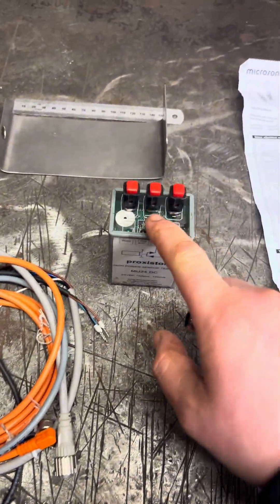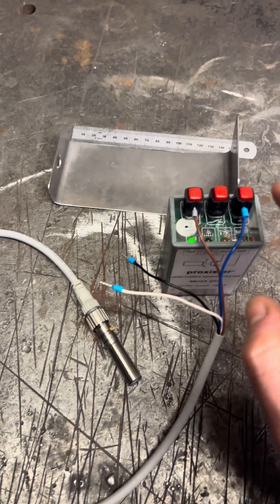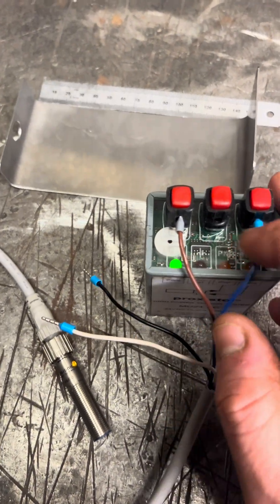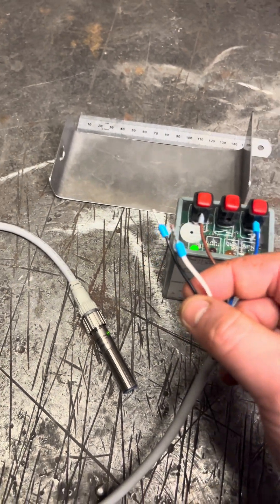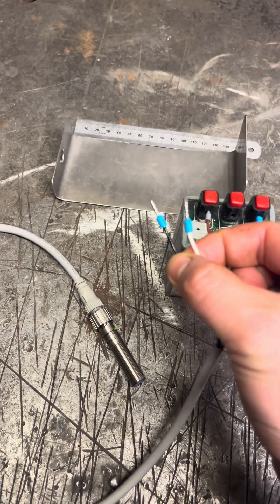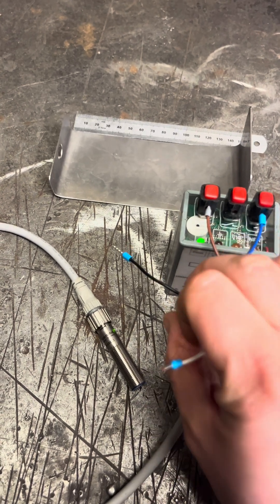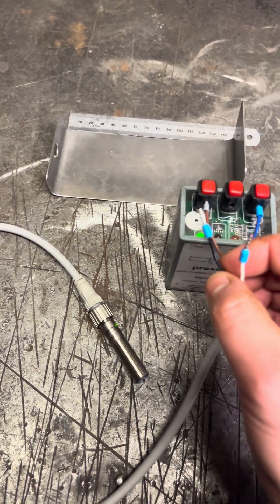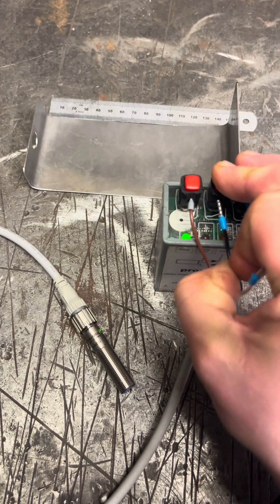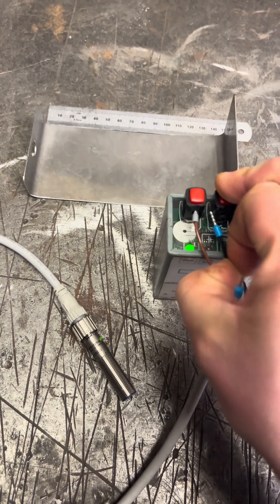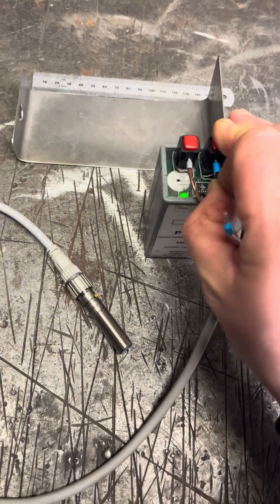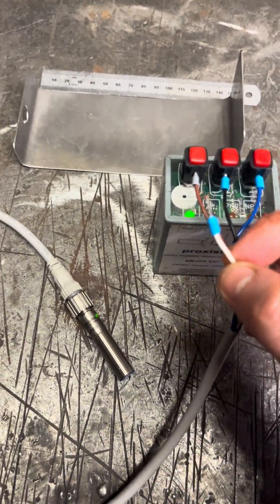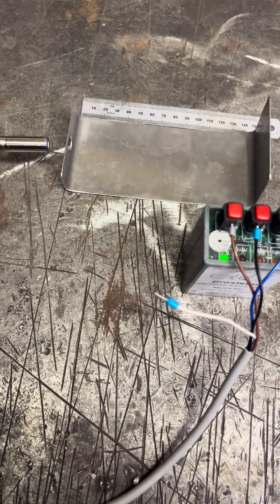As you can see, I've put my positive and my negative into the inputs. Now on a four-core cable, normally your black would be normally closed and your white is normally open. But on this, with your ultrasonic sensor, we've got to teach them. So your black is your input and then your white is your teach. That's what we're going to do. I'm just going to quickly show you how it works, this sensor tester.